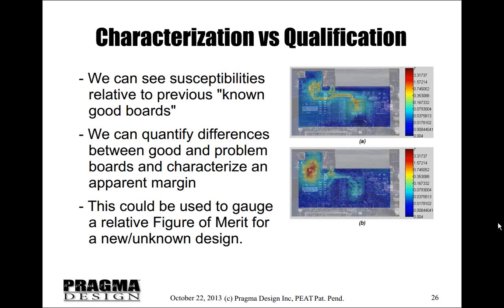It only takes about an hour to run a scan for some of these things. You don't have to have the device powered - it can be, but it doesn't have to be operating. In susceptibility scanning, the system has to be operating, and it has to be able to recover, so you have to have the tester programmed to reset the machine or cycle power or what have you. But with current reconstruction, it can be a completely dead board, and you can see what it does when you strike it.